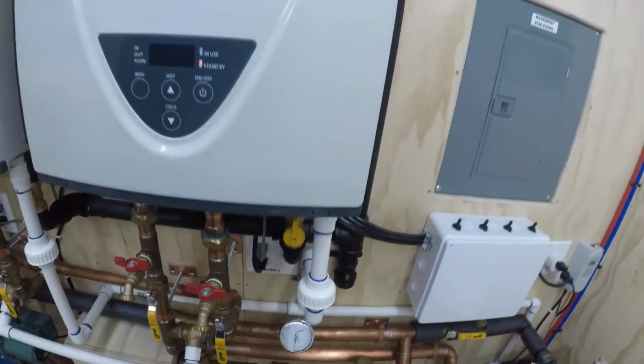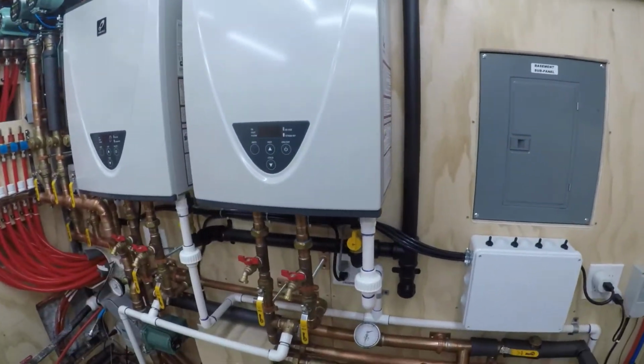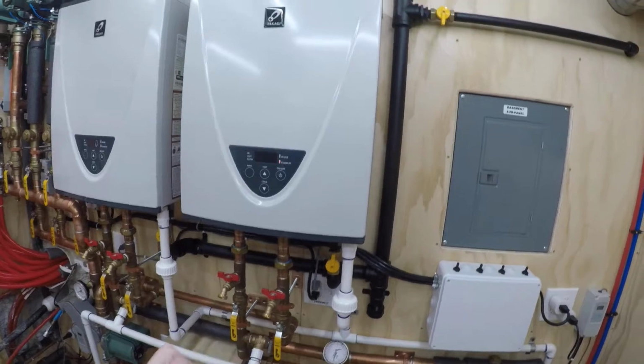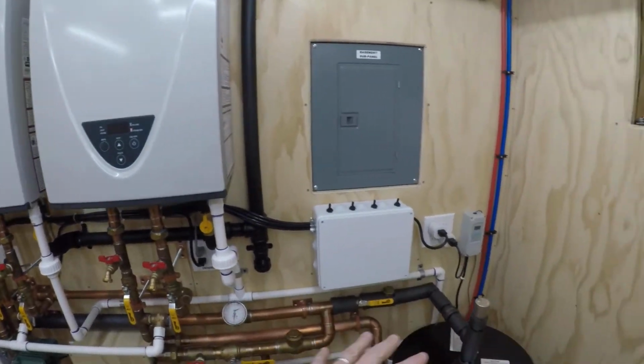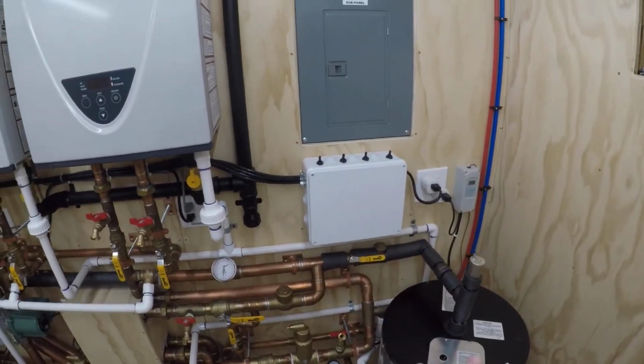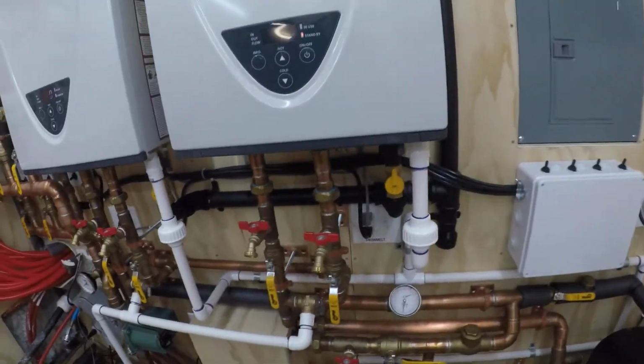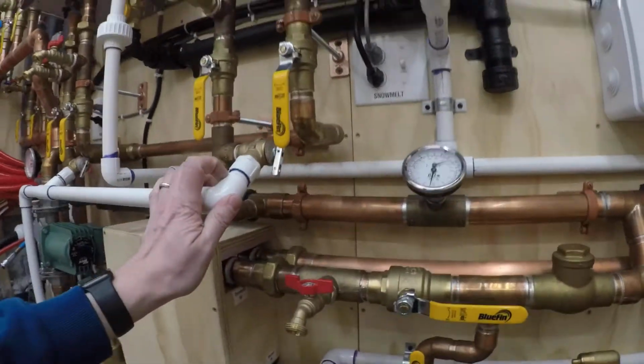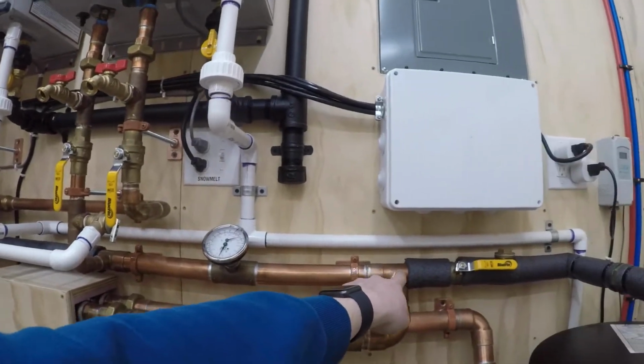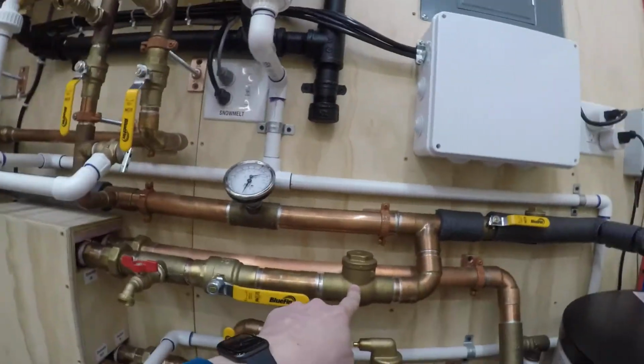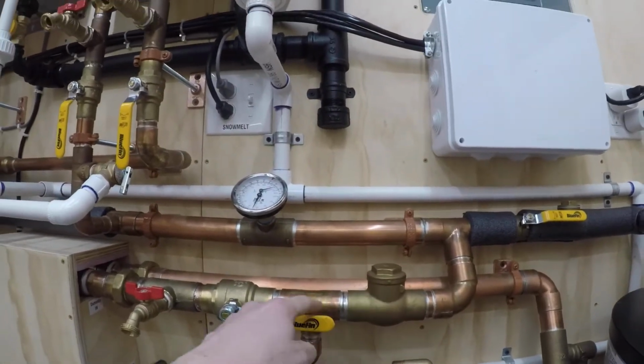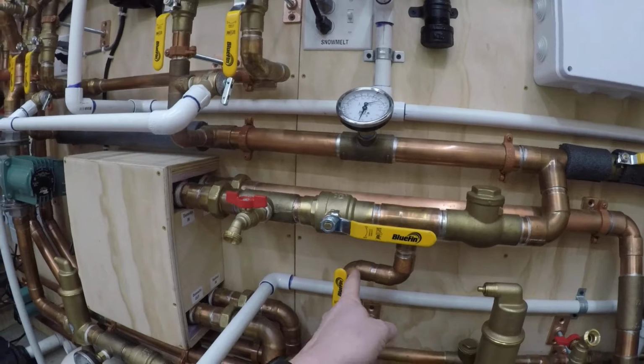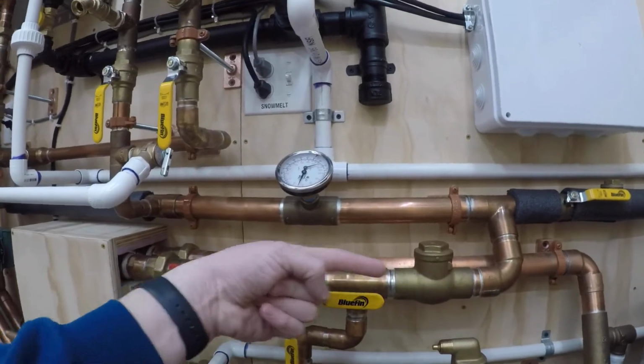So as far as the heater goes, the primary loop that I like to call it, you're basically taking the tank part, the domestic part of it, out of the equation. The primary loop comes down here, turns here, goes through another swing check valve, so the street pressure coming in from here cannot go backwards.